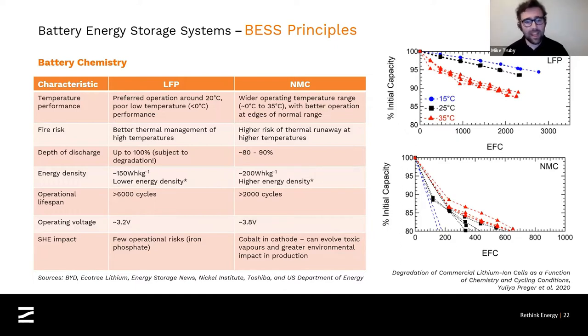But having said that, LFP batteries, we feel anyway, are much better suited to static operations. The main reason for this is fire risk. It's worth stating that battery fires are pretty rare. But where battery fires do occur in lithium ion batteries, they're NMC fires. The reason for that is that NMC batteries do have a property for thermal runaway if high temperatures aren't managed properly. LFP batteries do not have this property anywhere near to the same extent, and therefore they are much safer to manage. As I say, it is a relatively rare event, but when it does happen, it doesn't happen in an LFP battery.